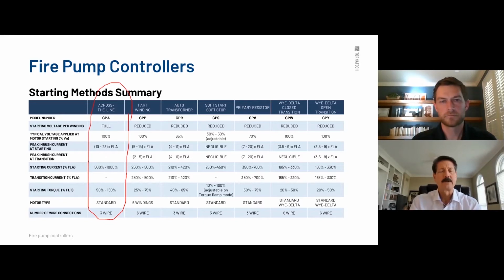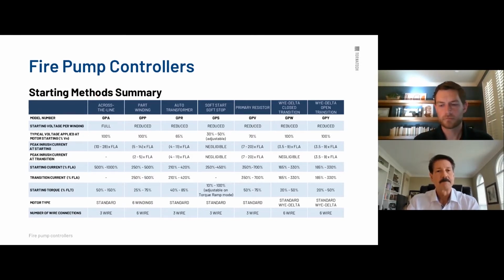Self-explanatory, whether you have 208 volt, 460, 480, the 3 motor leads you're seeing are going to get full voltage across each of the 3 phases of that motor. Typically the inrush you'll see is 6 times full load amperage for that particular motor. Again, that's an across the line starter. It's probably one of the most widely used in the industry.